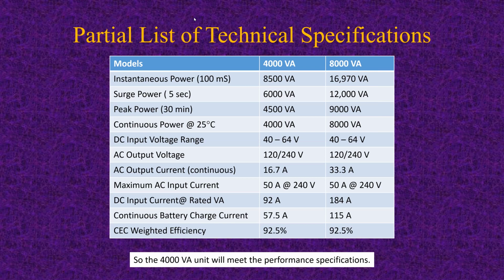How do we take into account loads with high startup demand, such as a well pump? Oh, perfect. Let's take a look at these specs. The timing is perfect. Notice the instantaneous power for 100 milliseconds on a 4,000 volt amp is 8,500 volt amps. So you get an extra 4,500 volt amps, or in other words, twice as much, because that's exactly what they're thinking about as a surge current. It'll give you 6,000 volt amps for 5 seconds, and they'll give you 4,500 per 30 minutes. So yes, they thought about that motor that needs to have a starting current, and most of these top quality battery backup inverters take that into account, and so they can start your motors.